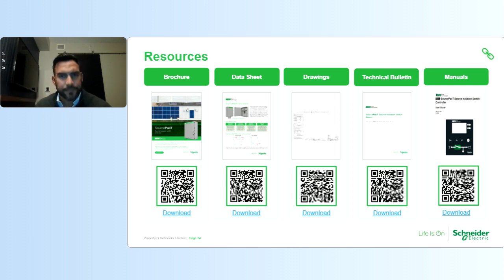And then we have a couple of white papers, a case study that's coming out for one of the single line diagrams that I've talked about earlier, as well as the installation manual here. So if you go through our SourcePacT controller, it goes through the entire sequence of operation. So very useful if you're looking to commission or test the system, right? A microgrid system, an energy storage system for backup power. It's almost a good checklist there you can reference to go step by step to make sure that you're following the sequence and making sure your energy storage system is operating correctly for that emergency or resilient scenario.